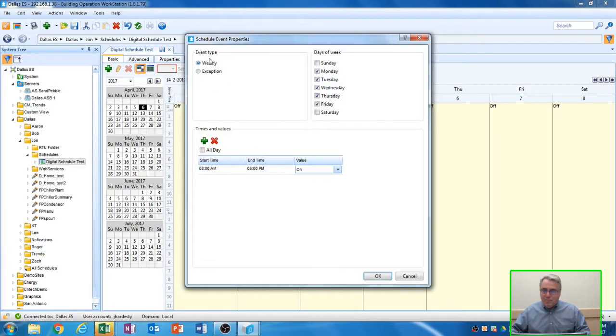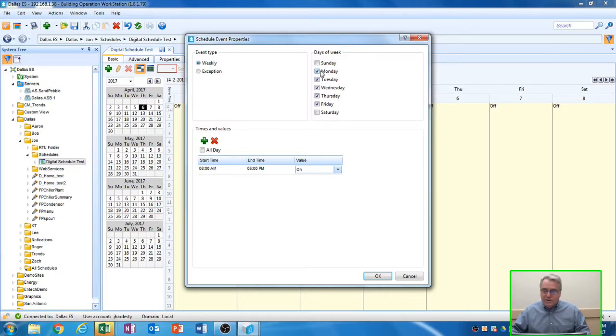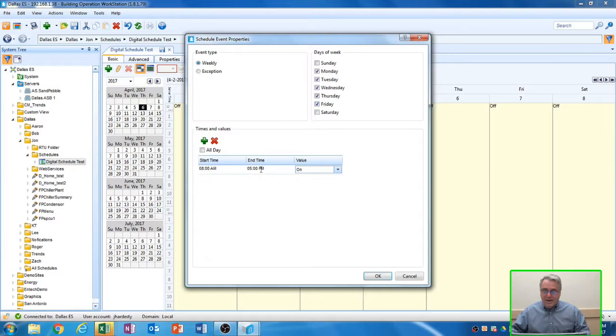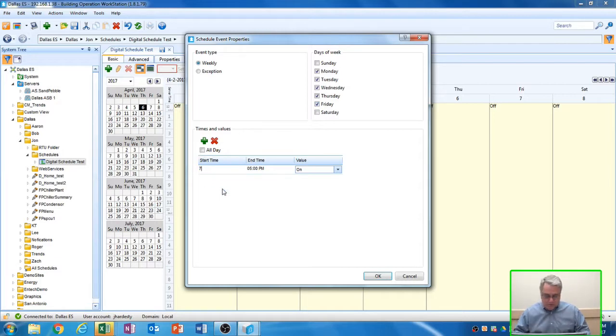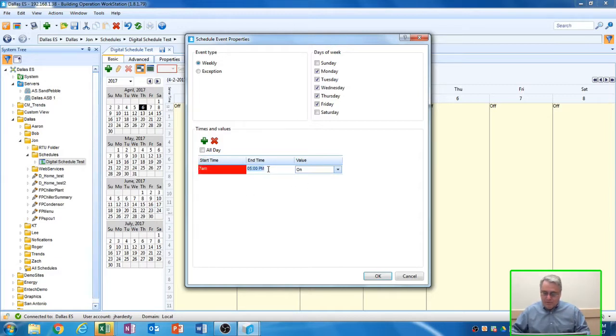When I click on that, the event type I want to select is weekly. Over here on the right-hand side, the days of the week that I would like this schedule to apply to, select those. It automatically defaults to Monday through Friday for you. It automatically defaults to 8 a.m. to 5 p.m. for your start and your end time. But I want to change those. We start at 7 a.m. So I'm going to go down here and change the start time to 7 a.m.